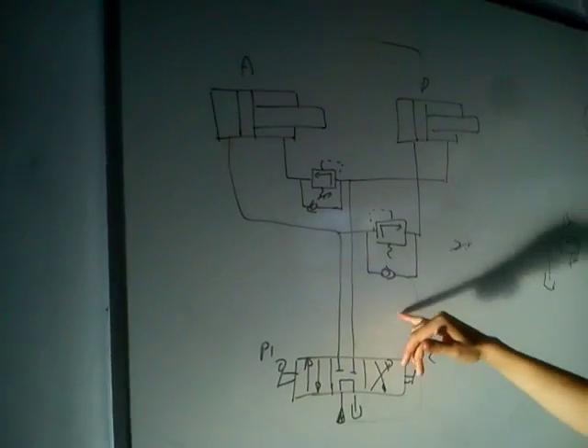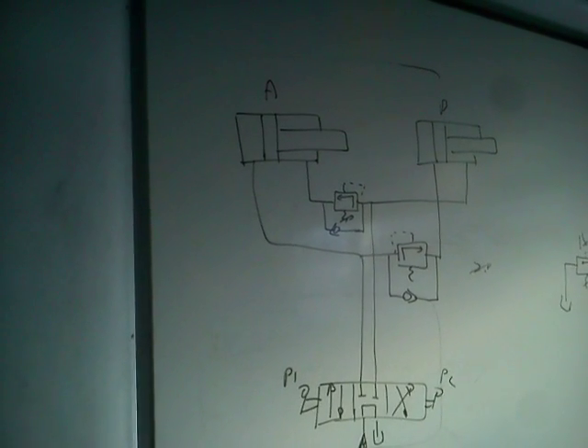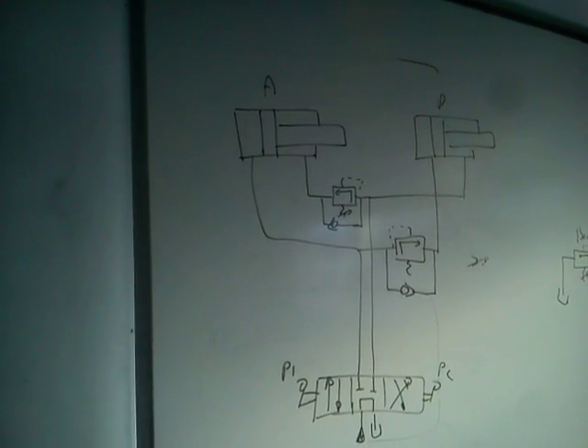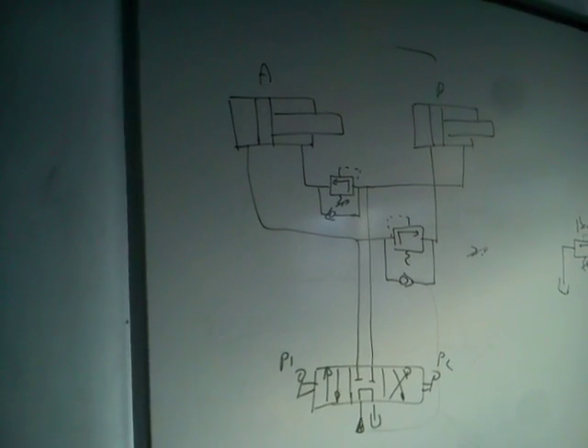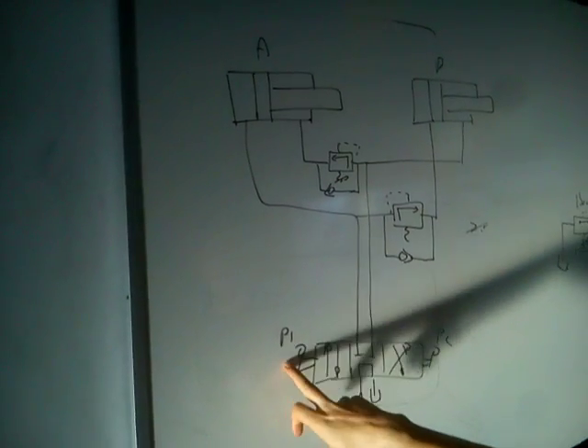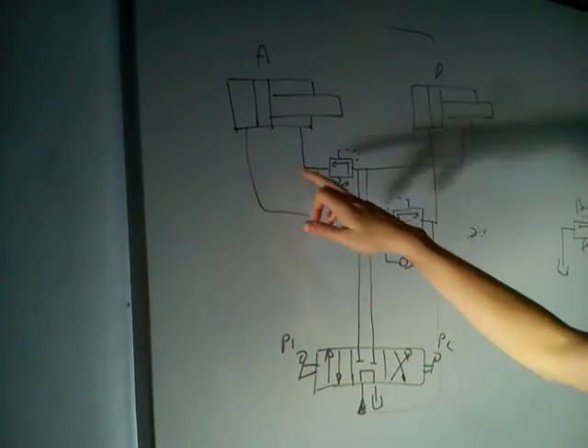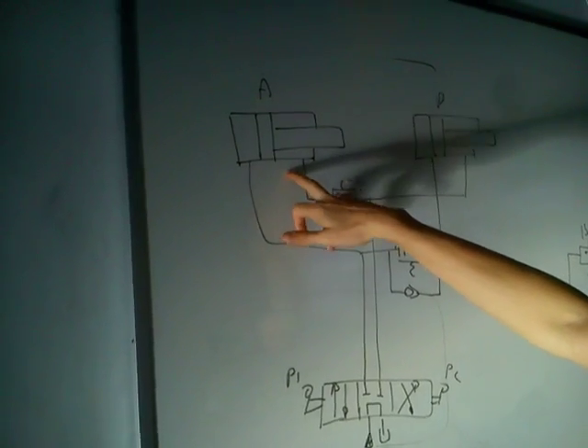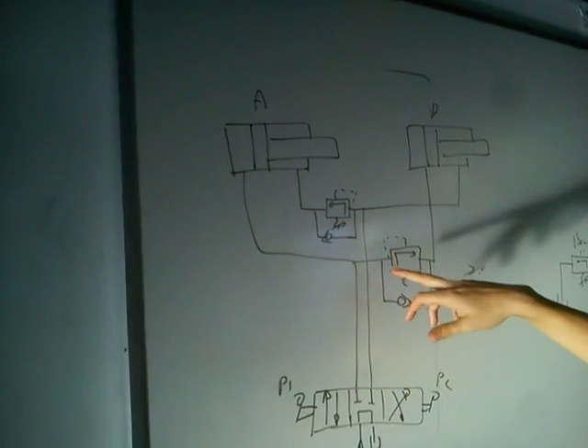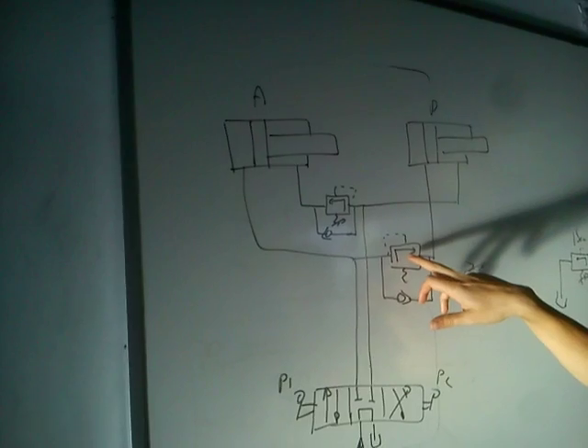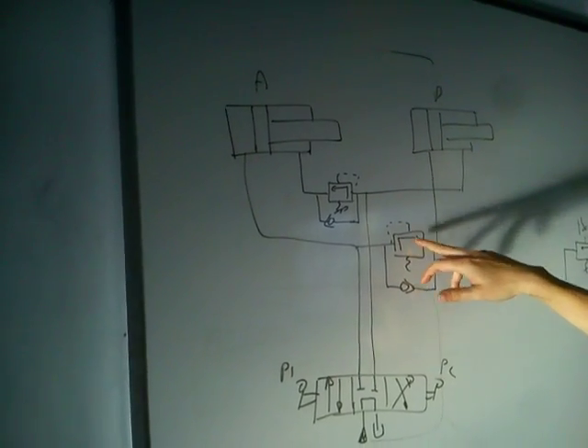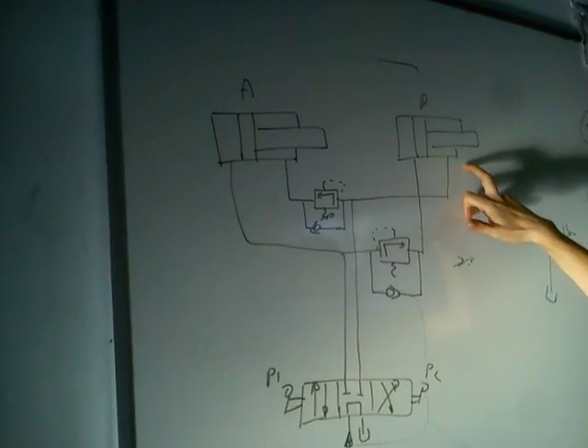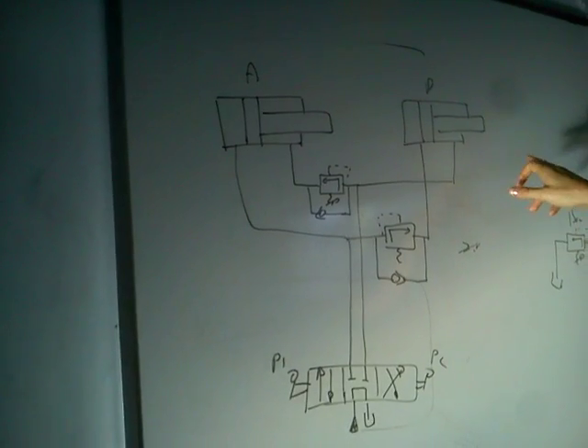Here we use two pressure relief valves as sequence valves. When we push P1, first we obtain the forward movement of the A cylinder, and then the pressure pilots the pressure relief valve and starts the B cylinder going out.